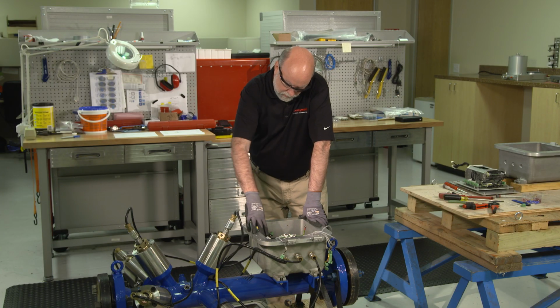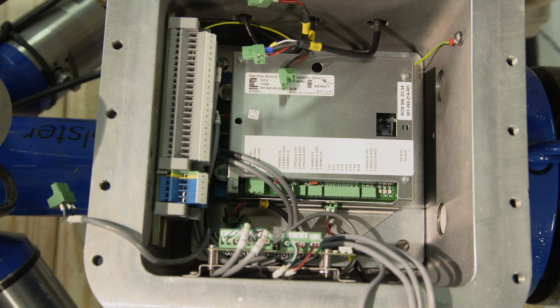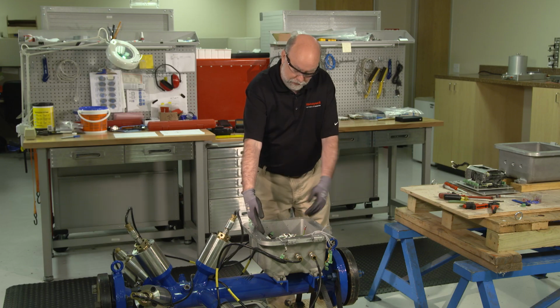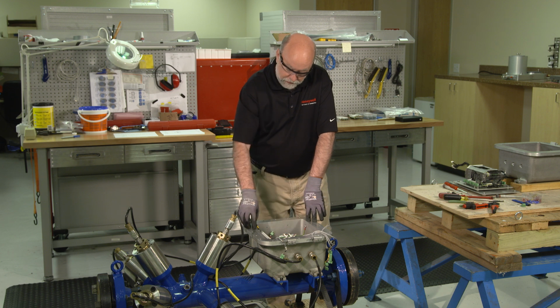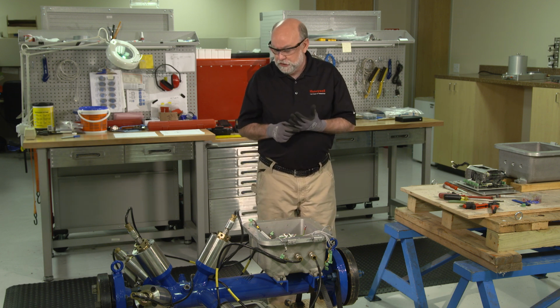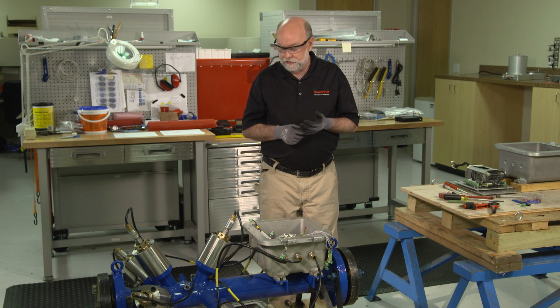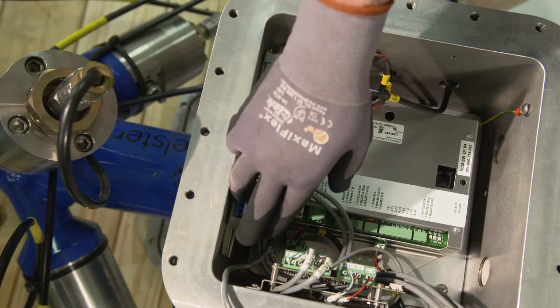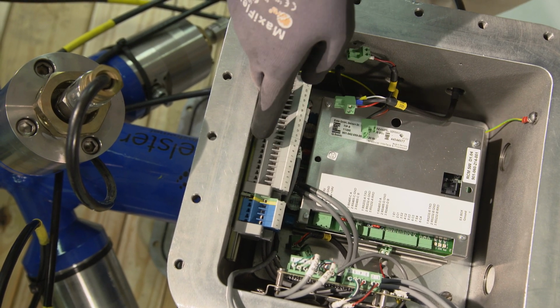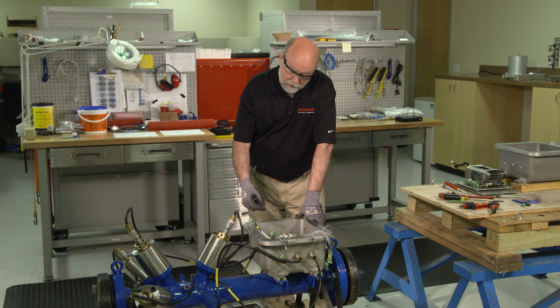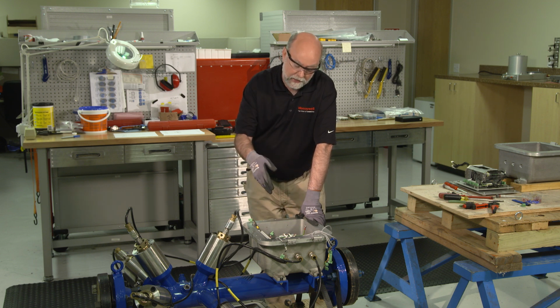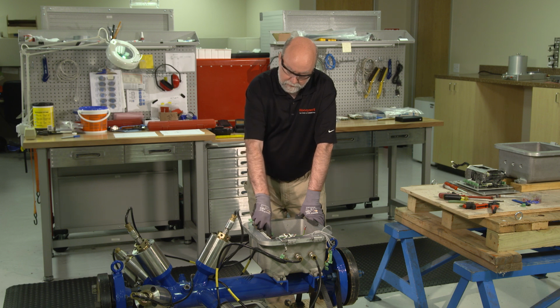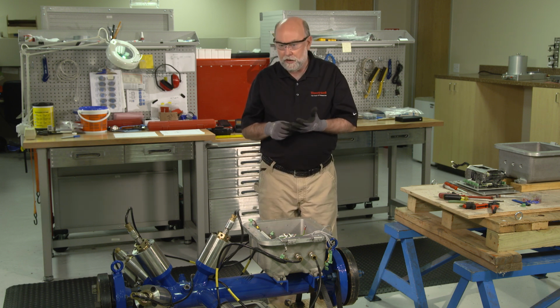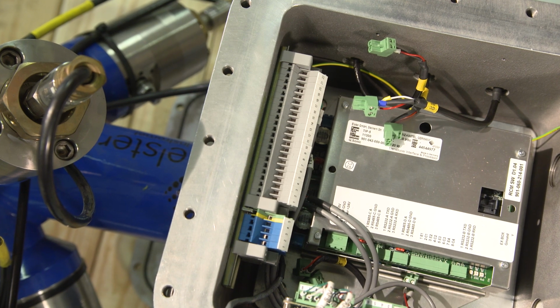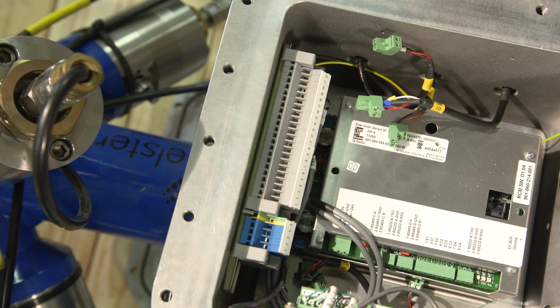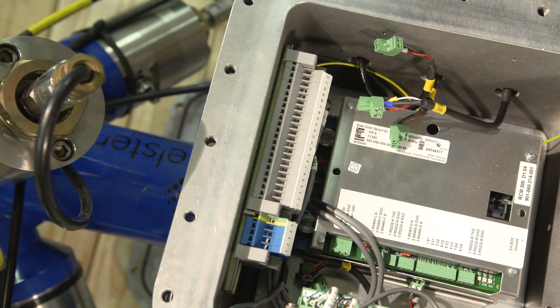While we're at it, I'm looking at a terminal block here that doesn't have any wiring in it, but of course your meter in the field has wiring coming into the box as well as going out. So before starting this, you need to de-energize all the circuits as I mentioned previously. Also, when you determinate these wires, meaning loosen the screws in the terminal blocks and remove the wires, you need to mark those wires so that you know how to land them again after we've installed the new upgrade kit. They need to be marked for identification. They also need to be taped. Even though they've been de-energized, we don't want anything shorting against an earth ground that could create a problem. So just for safety's sake, we want to tape those wires off.